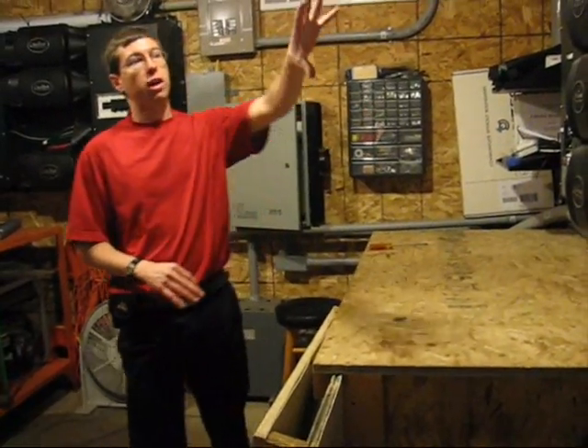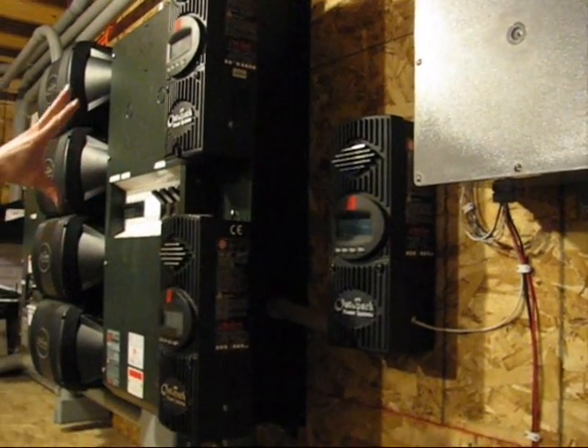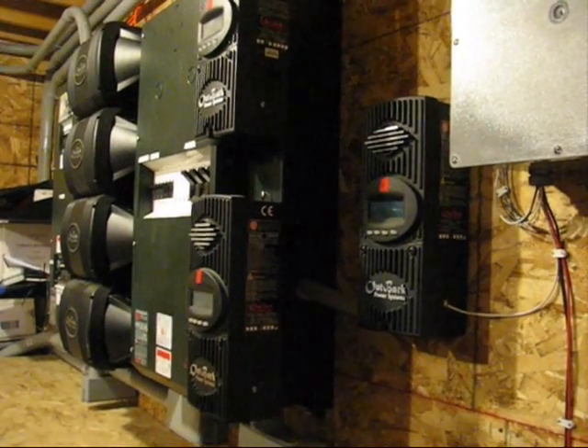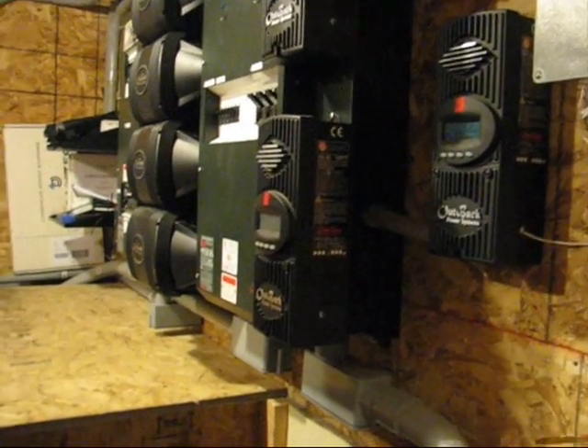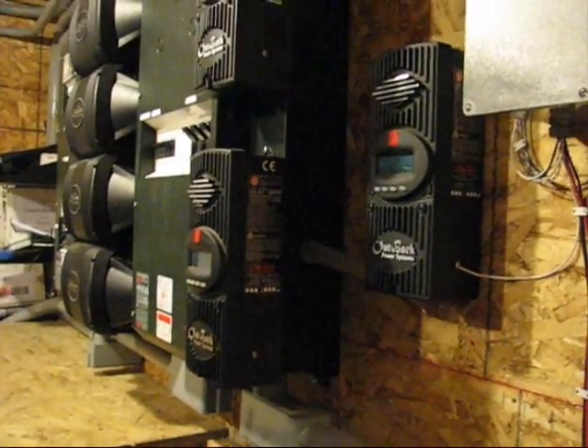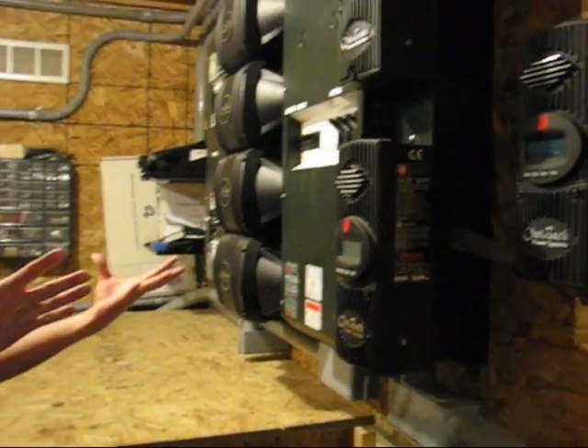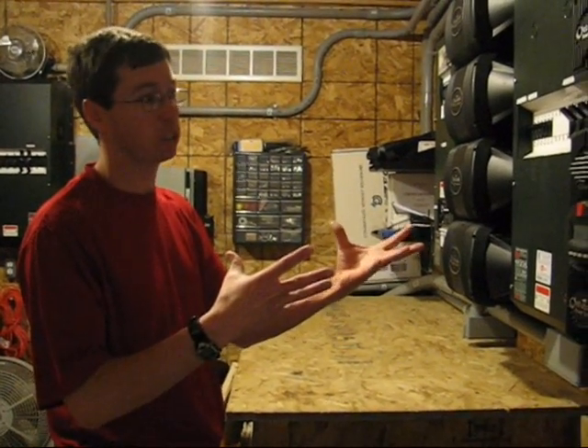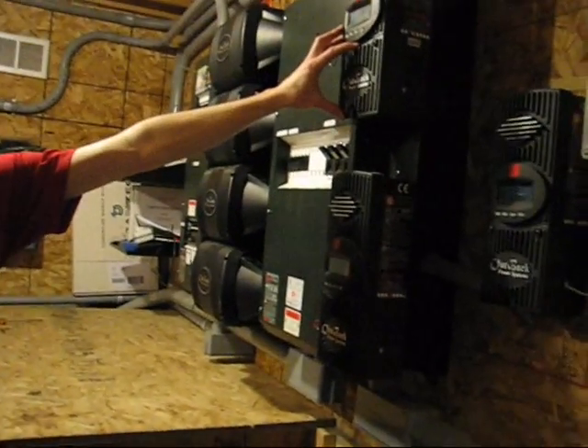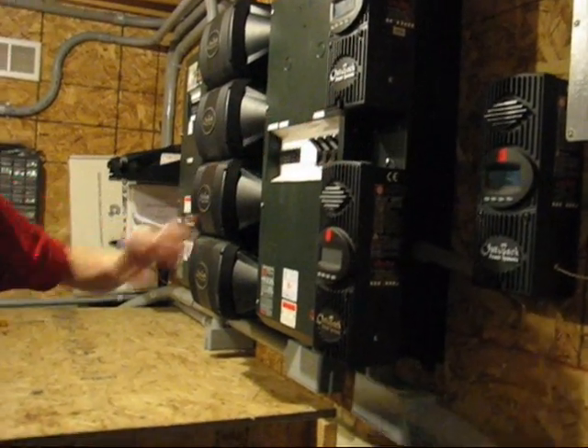To the right of the system, there's one unit for each of the three solar panels. What they do is take the power in off the solar panels and step it down to a voltage appropriate for the battery bank. They also find the maximum power point — when a solar panel has no load attached, it can have a high voltage of something like 100 to 120 volts. These units find the right loading characteristics to get the most power out of the available sun.